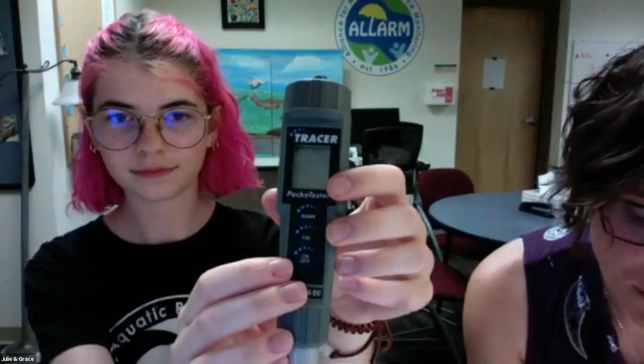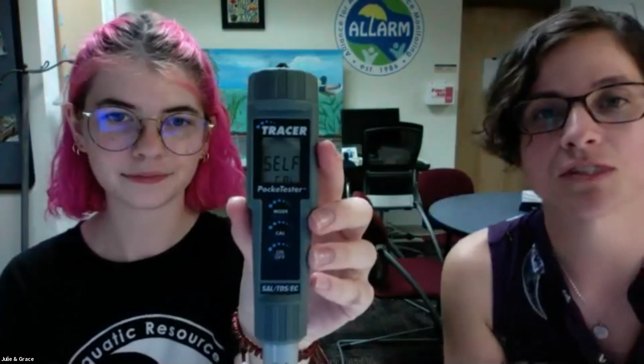So one of the things we're going to do is you can remove the batteries, you can replace the batteries, but the first thing to try is actually resetting the meter. So you're not going to do this. We just want to demonstrate this because we don't want to clear your calibration. So what Grace is going to do is she's turned her meter off. And then we are going to simultaneously press on, off, cal, and mode all at the same time. That was a really great look. First try, it got a DFLT, so it's going back to default.